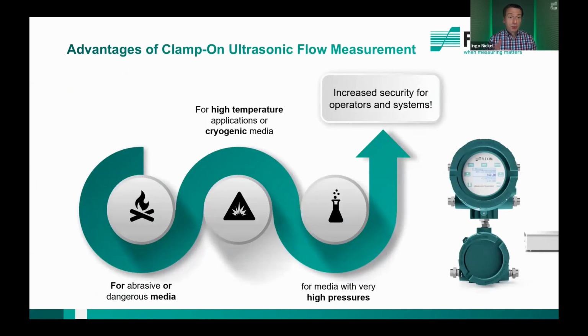What are the advantages of using a clamp-on ultrasonic flow measurement system? And why is it interesting for the chemical industry? Because it has several advantages which can tremendously increase the security for operators and for plants. Ultrasonic flow meters can be used for very dangerous, corrosive, and abrasive media. They can also be used for very high temperature applications, but also for cryogenic media. And also a very important point, which I will explain later on, it's also a very reliable solution for very high pressure applications like the LDPE process.